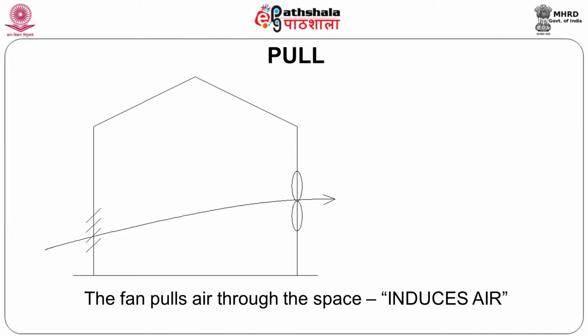This is a very simple detail like one sees in any toilet. You go to a toilet, you find that there's a small exhaust fan throwing out air. That is called pull ventilation. Ideally for such an application, air inlet comes in from the door. The exhaust fan maintains the place at a negative pressure and throws out the vitiated air.